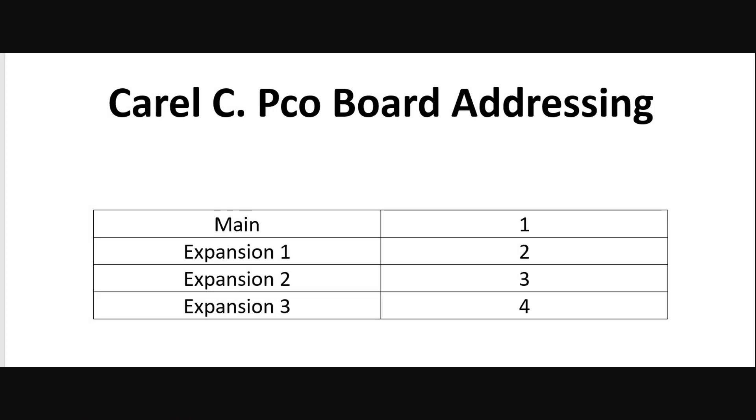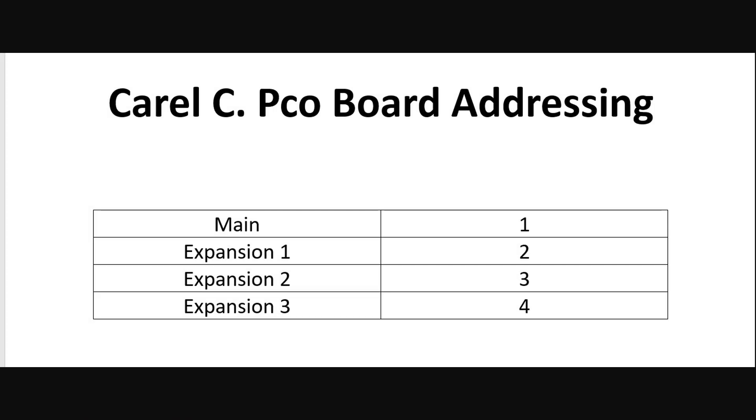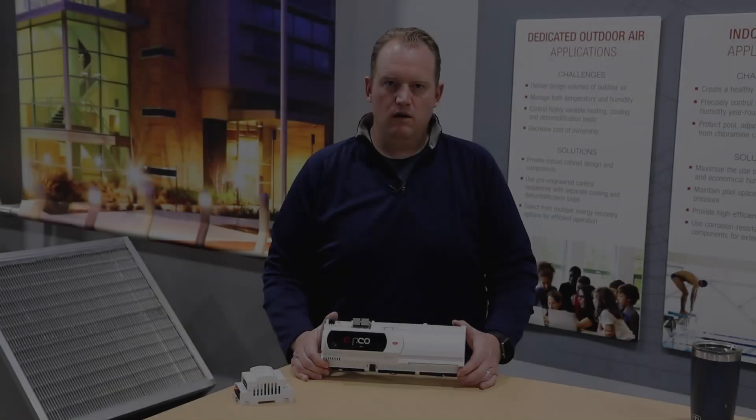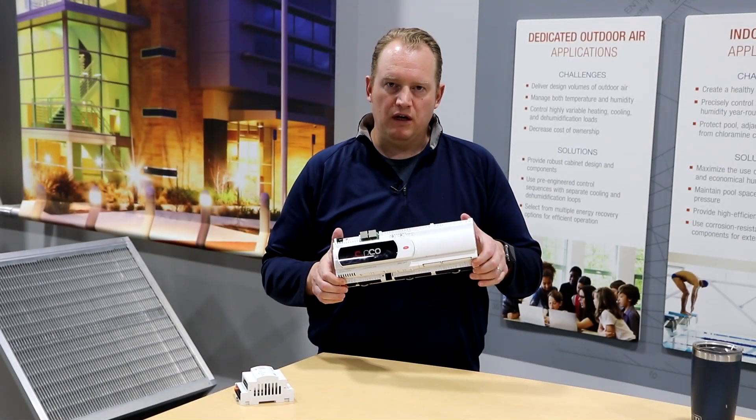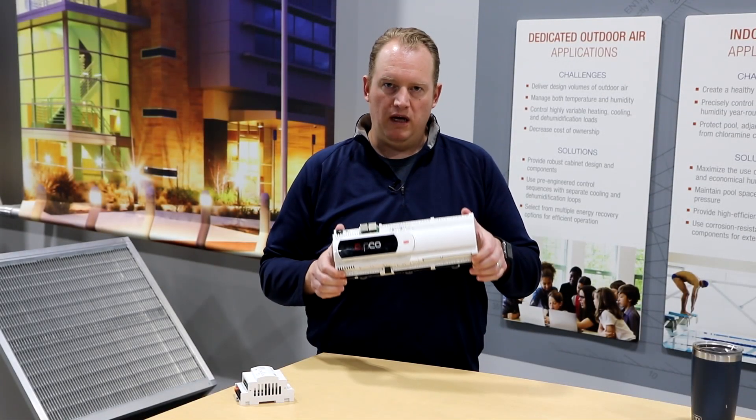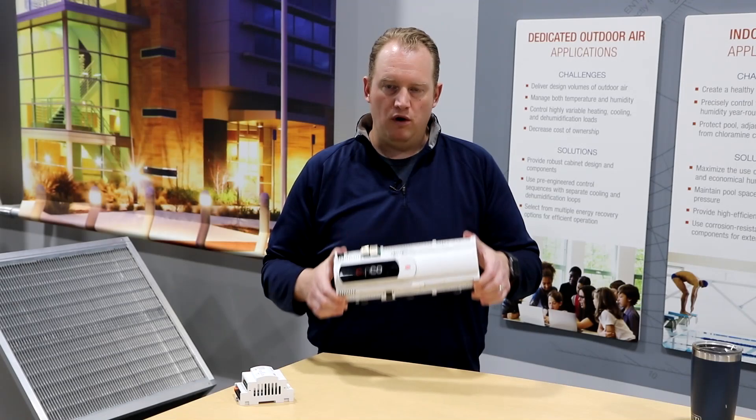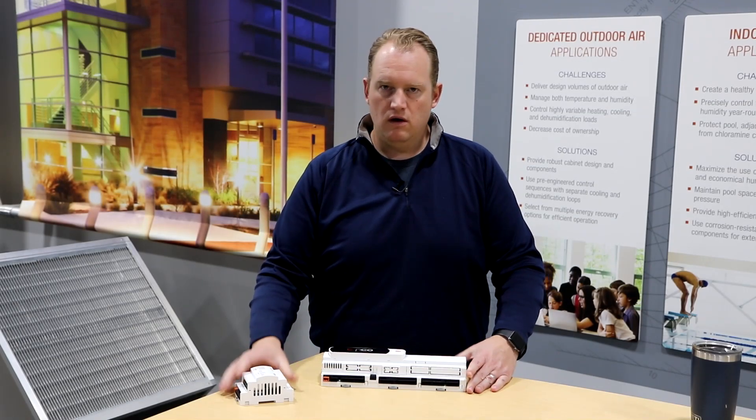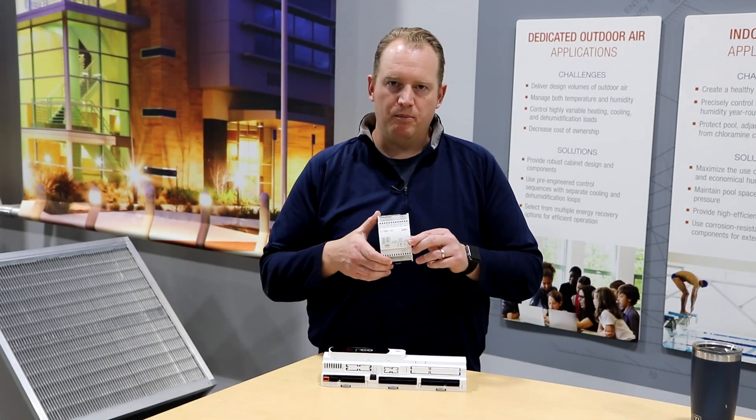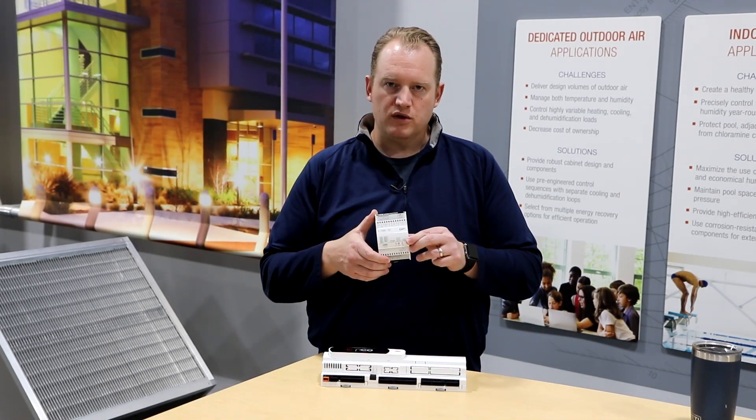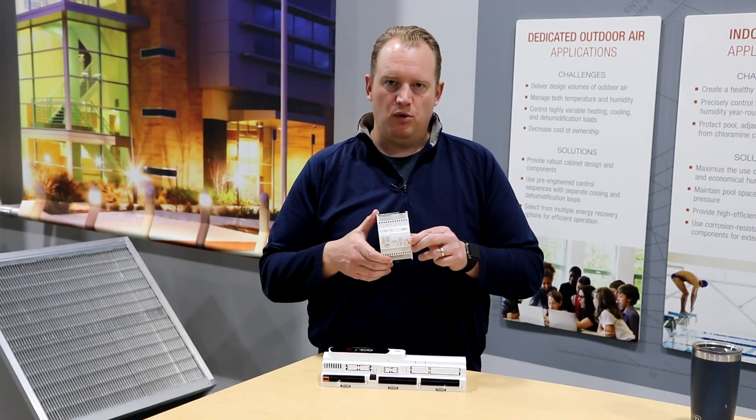The next step is to determine whether the replacement controller is a main board or an expansion board. A main controller or main board would be addressed 1. Each expansion board will be addressed as the number of expansion plus 1. For example, expansion 1 is addressed to 2 and expansion 2 is addressed to 3 and so on. The large pCO can be a main controller and an expansion board. The small pCO is always going to be an expansion board.